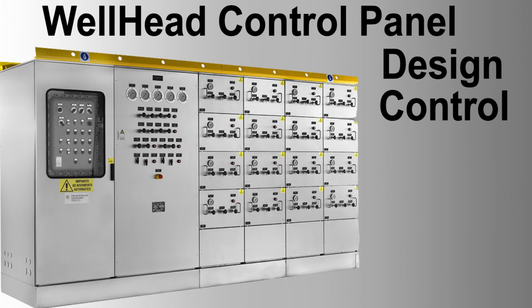Operation: 1. Normal operation. The WHCP maintains hydraulic pressure to keep the SCSSV open. 2. Shutdown. In case of a high-pressure alarm, low hydraulic pressure, or manual ESD activation, the PLC RTU vents the hydraulic pressure, causing the SCSSV to close. Control loop. Closed loop. The pressure transducer provides feedback to the PLC RTU, which adjusts the hydraulic pressure to maintain the SCSSV in the desired state. Feedback: real-time pressure data from the transducer. Control signal: hydraulic pressure regulated by the PLC RTU.